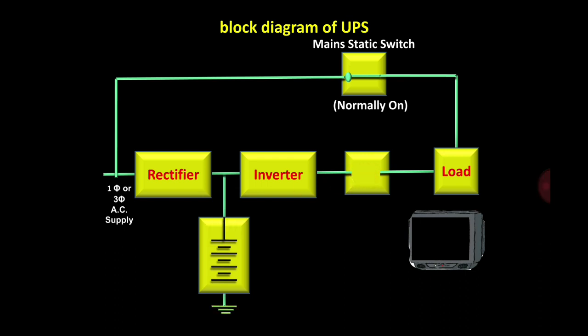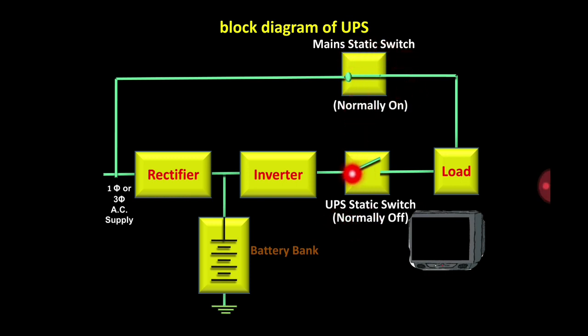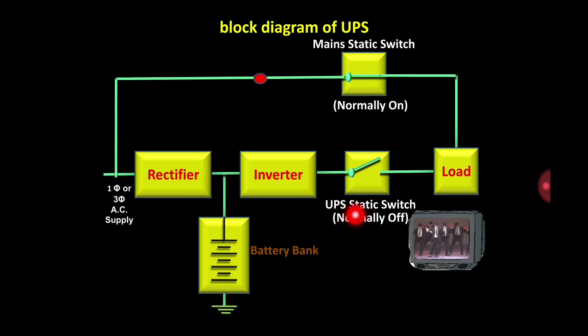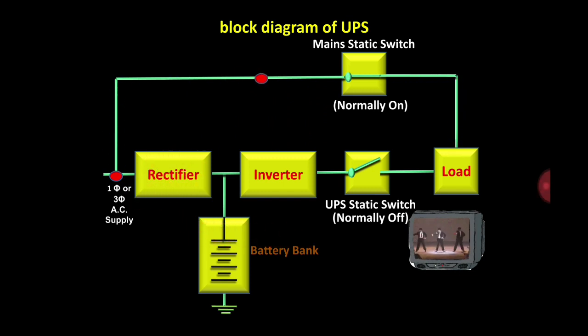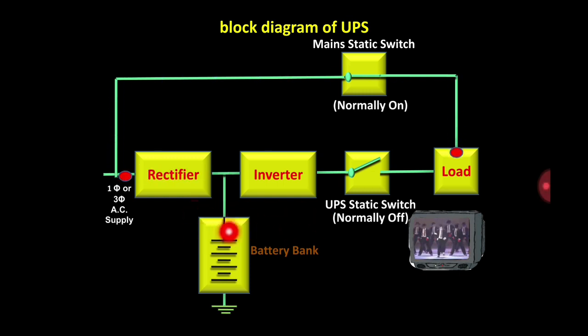When the main supply is available, the UPS static switch is normally OFF and the main static switch is normally ON, because the chances of having main supply available are more. So the load is receiving supply from the main line, and at the same time the battery is getting charged. Since the battery requires DC, we use a rectifier — the rectifier converts the AC supply into DC and charges the battery.